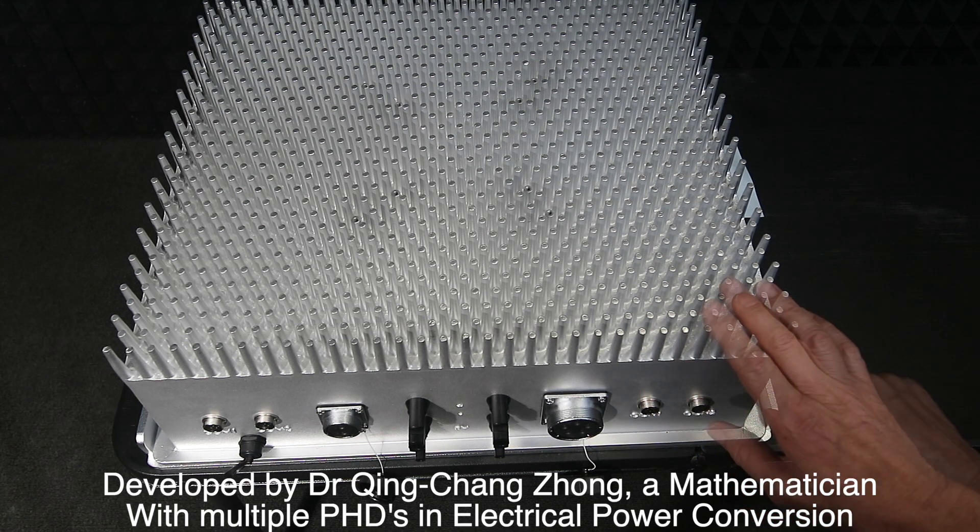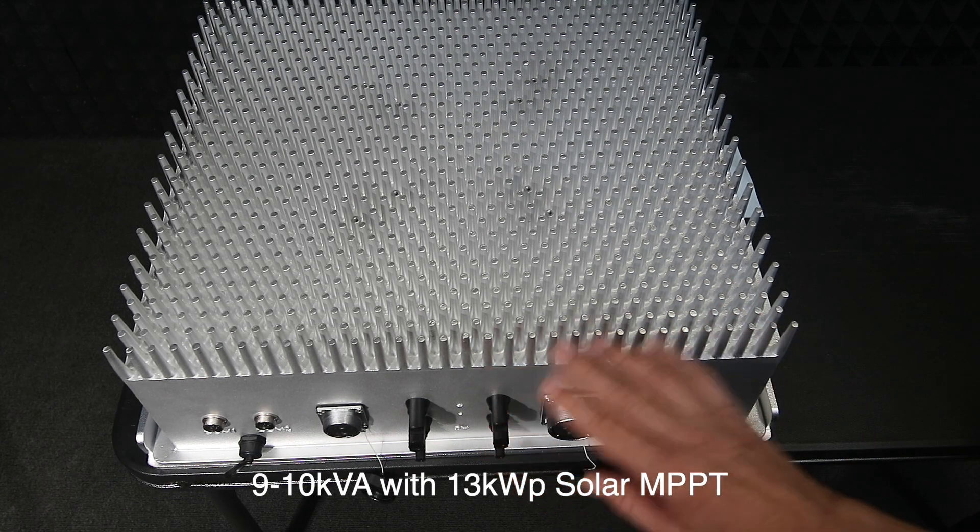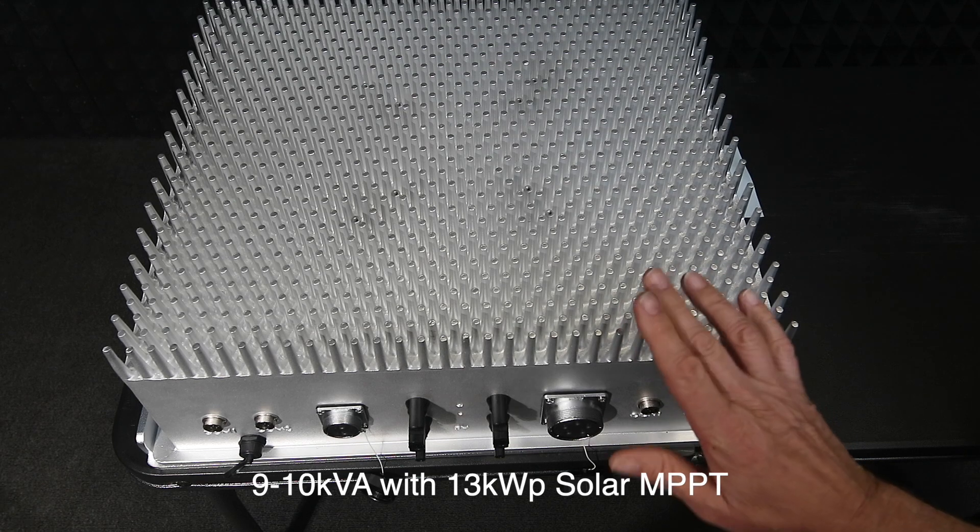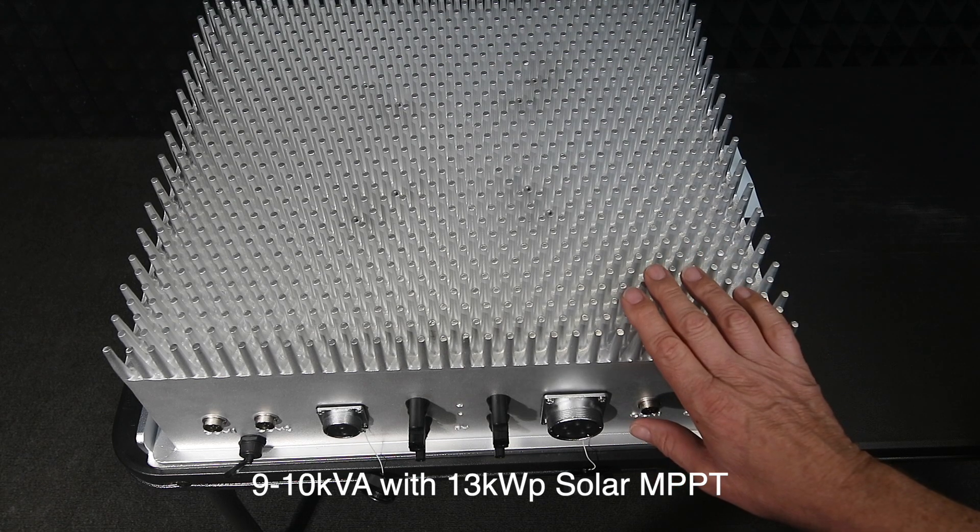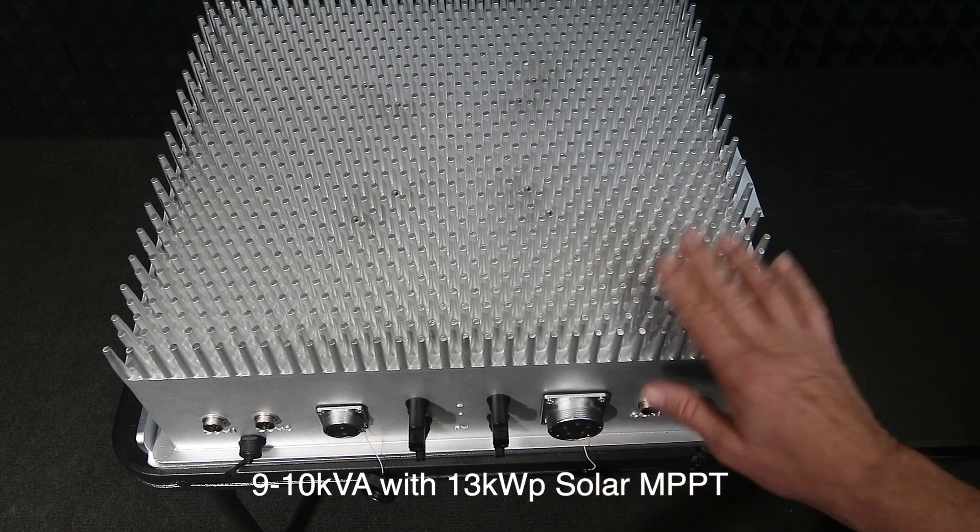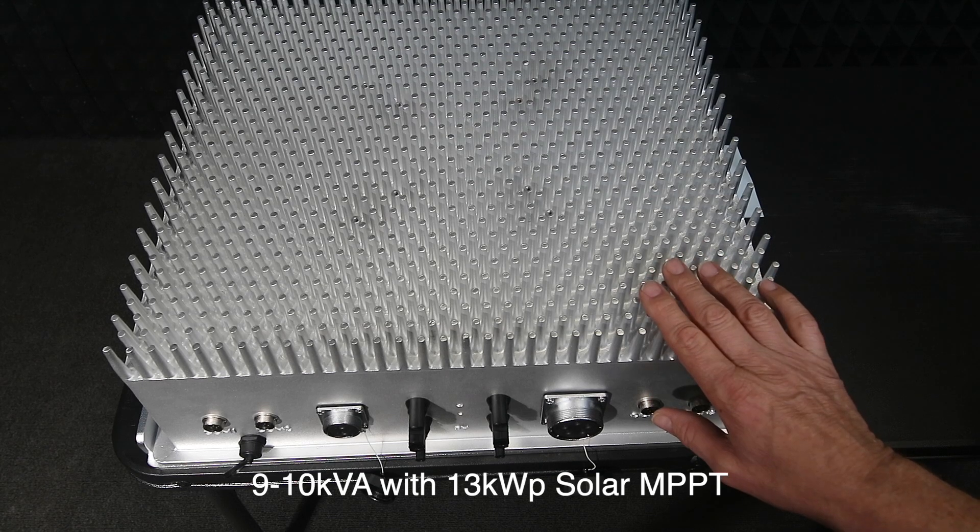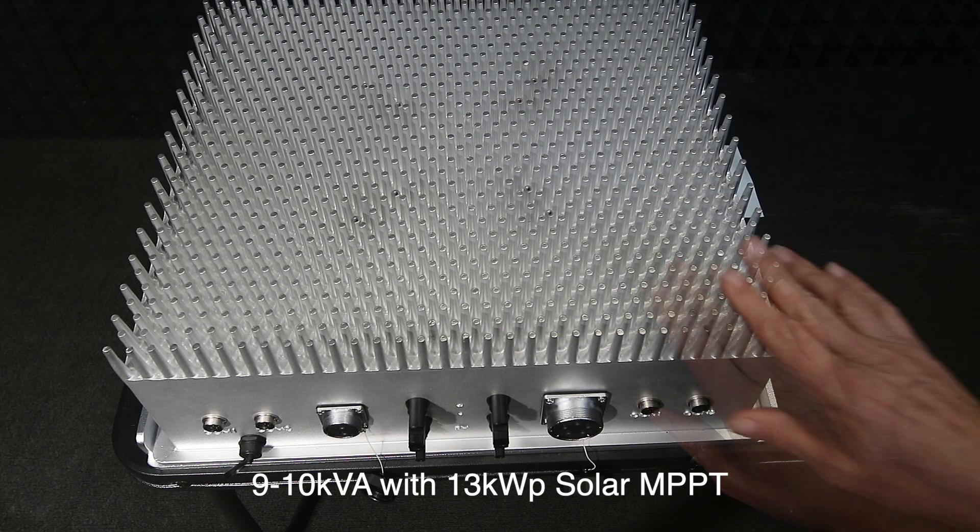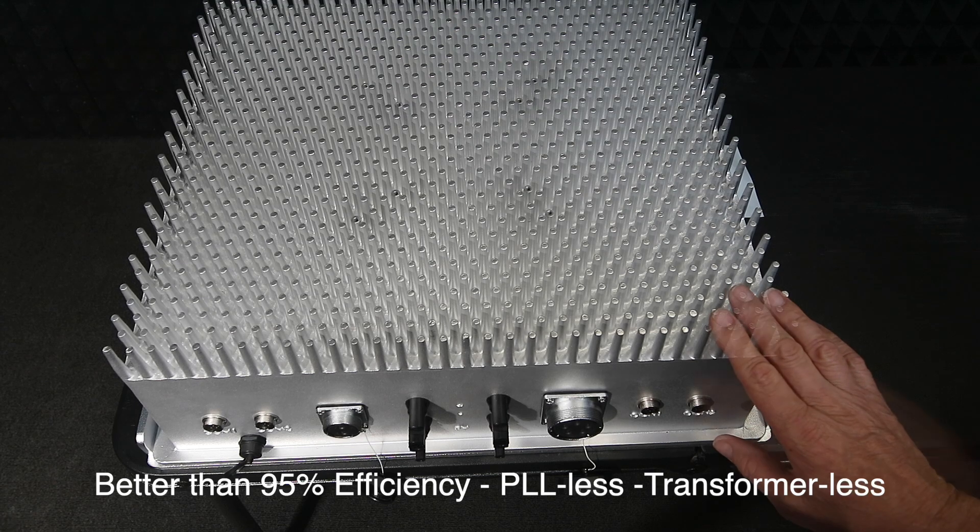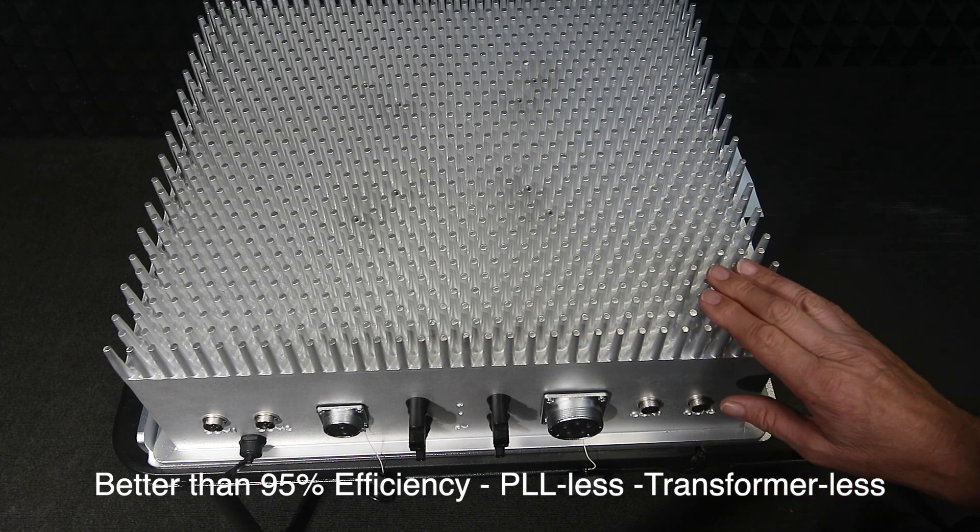Solar input to it is about 13 kilowatts. The unit is 9 to 10 kVA in that range—it can do a boost up to 12, but normally we say this is 9 to 10 kVA. The efficiency is better than 95%. The unit is PLL-less, that's Phase Lock Loop—it doesn't have that in here.